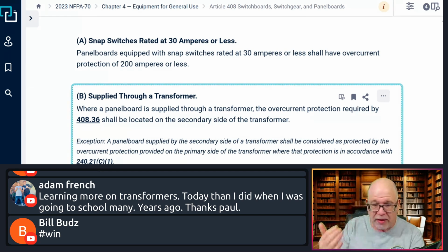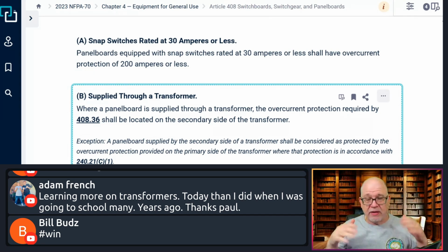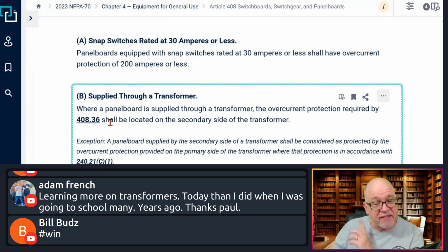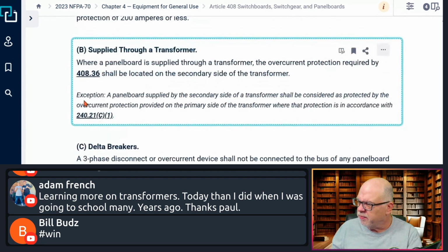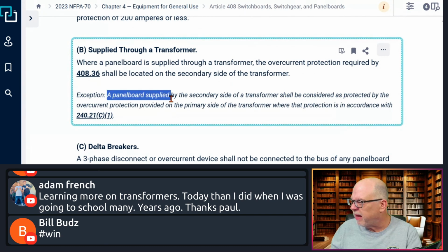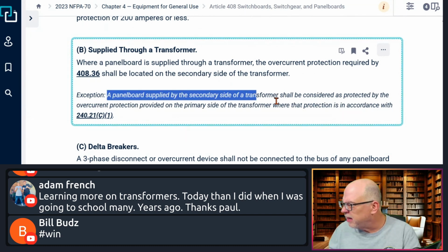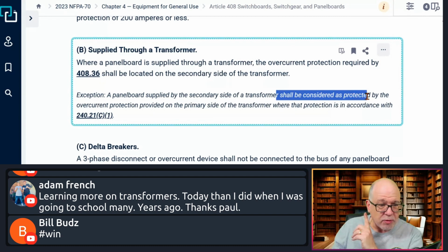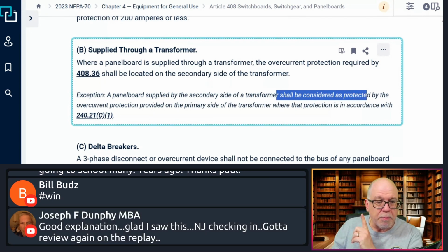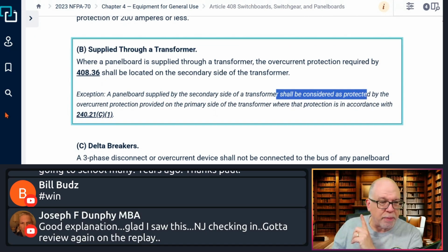That's overcurrent protection for the panel board now, okay, located on the secondary side of the transformer, either before it separately or inside of the panel board. Usually it's going to be a main breaker, okay? That's all we were saying, and that's what you're probably commonly going to do. The exception that it was talking about is right here. This is the exception that I was talking about. It says, look, a panel board supplied by the secondary side of a transformer shall be considered protected. Okay, we're talking about that panel board. It shall be considered protected by the overcurrent protection on the primary side of the transformer where the protection is in accordance with 240.21(C)(1).